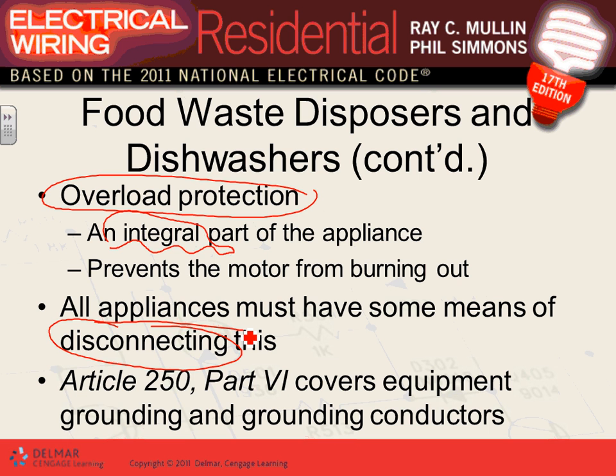Equipment grounding. So for grounding for all these appliances, guys, very simple. They all come with an equipment grounding conductor. You have to provide an equipment grounding conductor that ties to the frame of the air handling unit, the dishwasher, as well as the disposal.